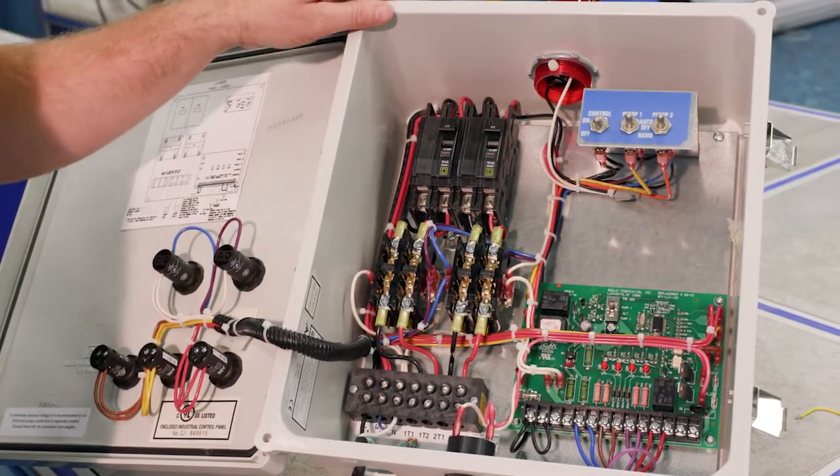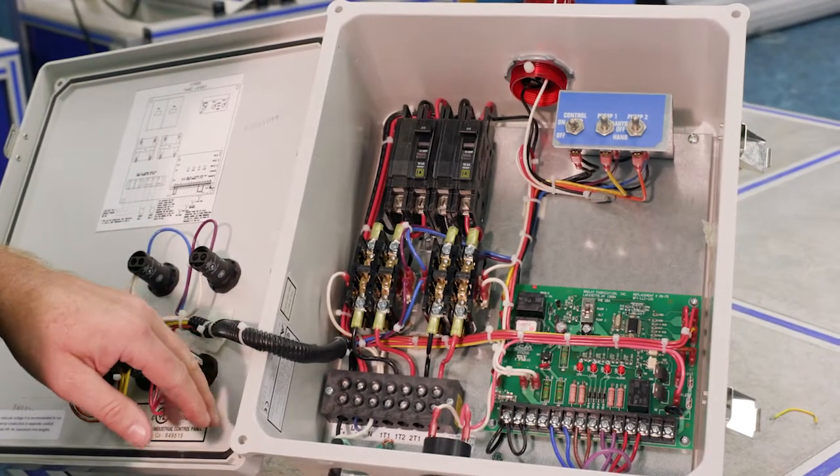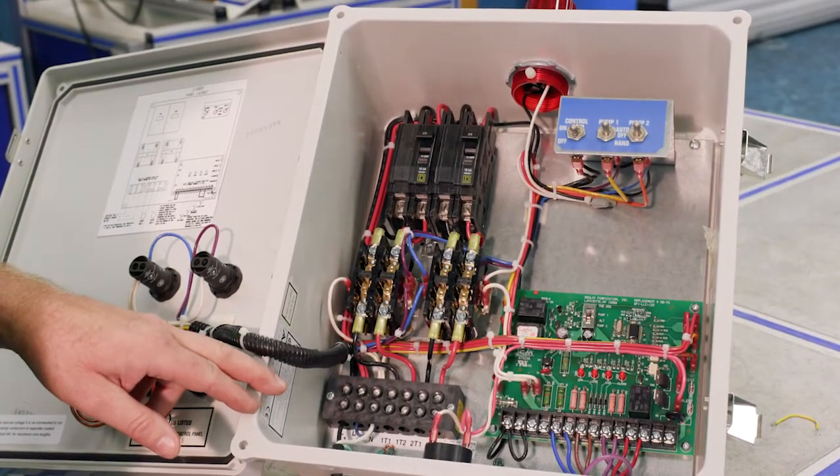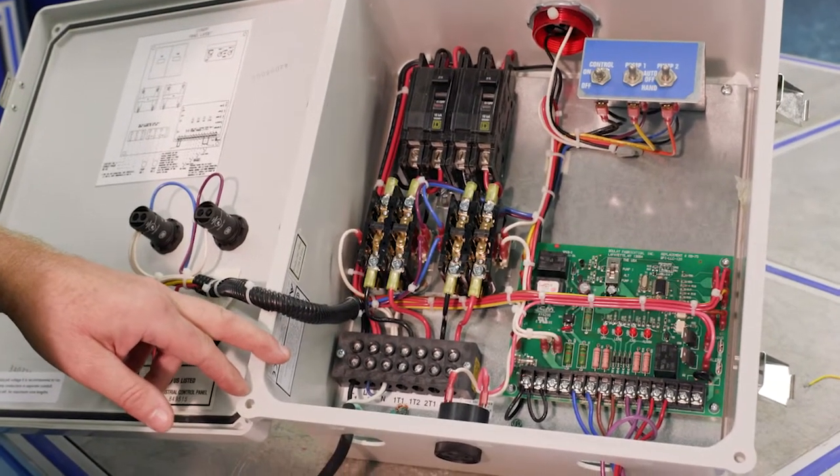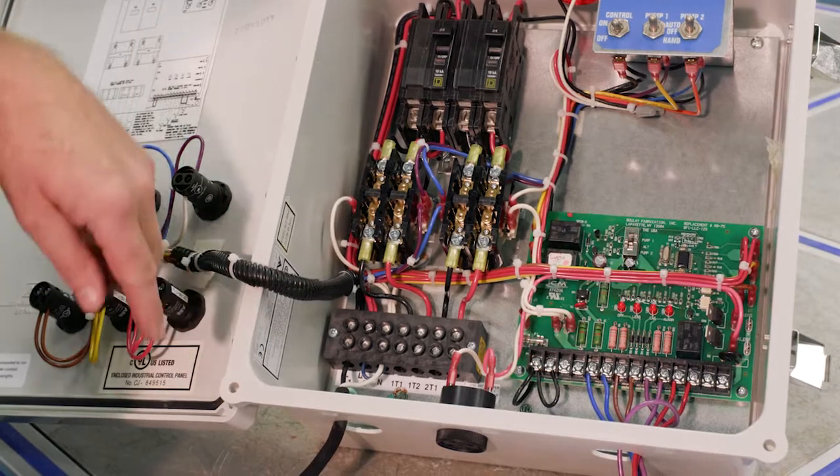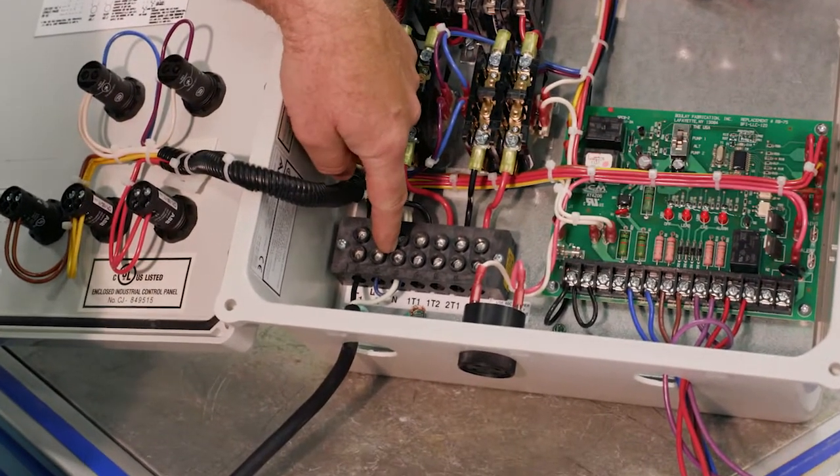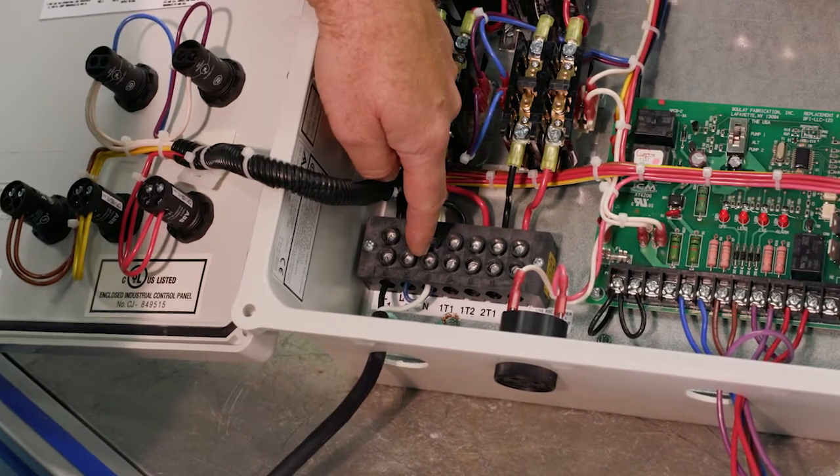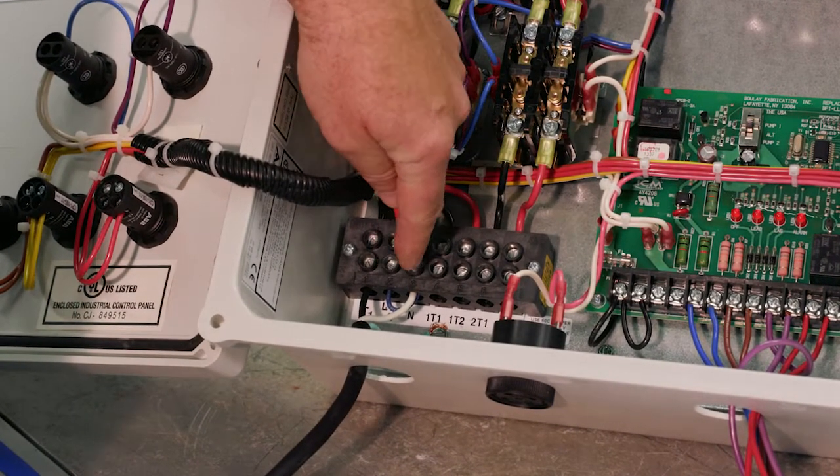The first note there is for 120 volt operation. If we look at that on the wiring diagram, the note says for 120 volt operation, use terminals L1 and N. So we're talking about this area here. And then it says jump terminals N and L2.